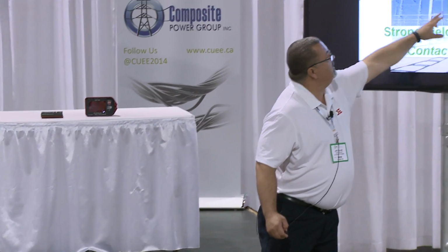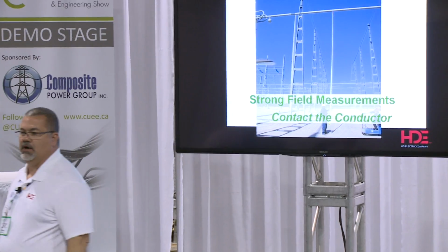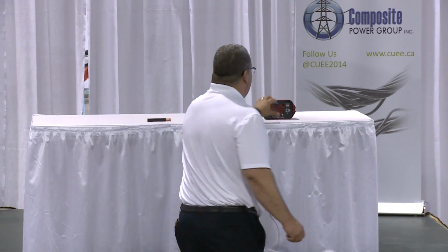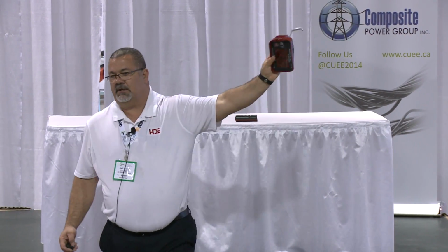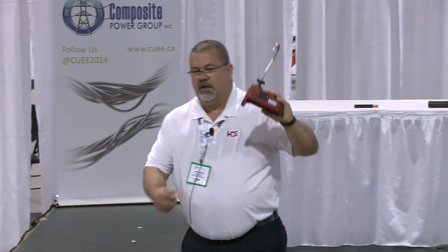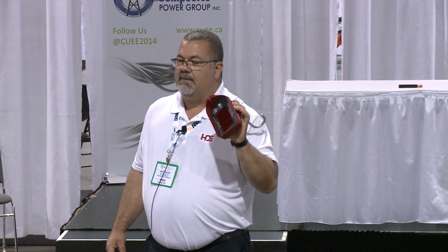As you'll see here, that graphic is very small, but you can see the hot stick here in the center. Got a gentleman down here holding the hot stick. He's going up to a bus bar in a substation. He's using a detection device similar to this. He's got a bigger hook on it, but we're actually contacting the conductor. We're still using an electric field type measurement here to do that.